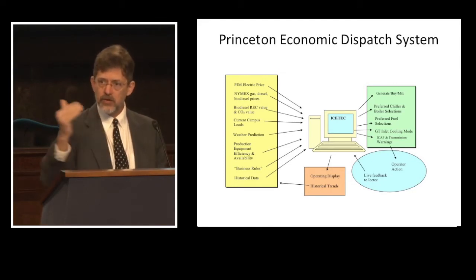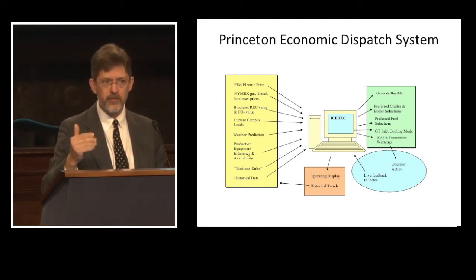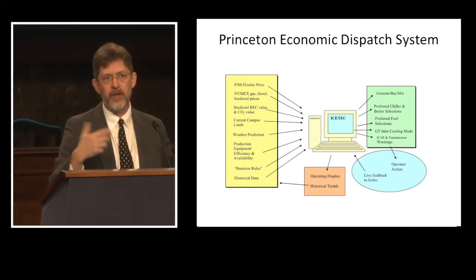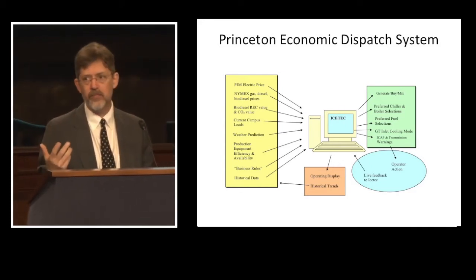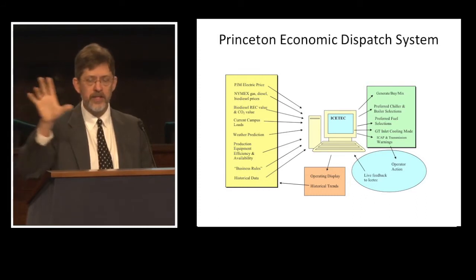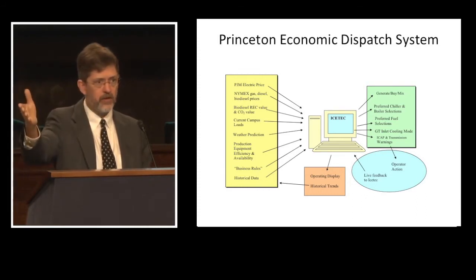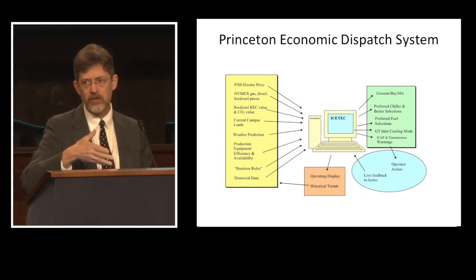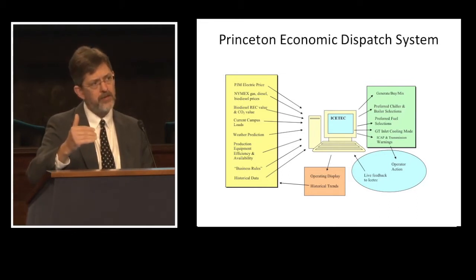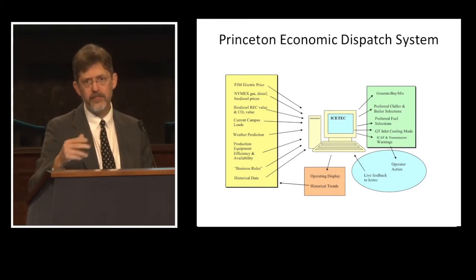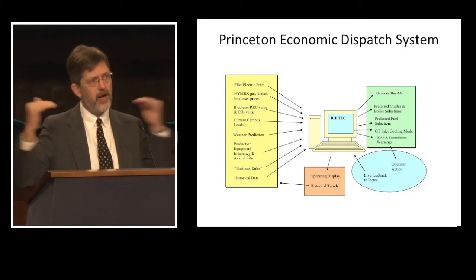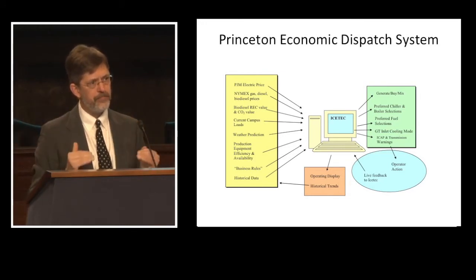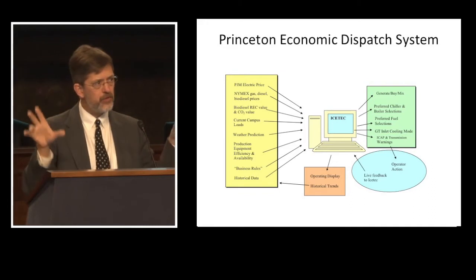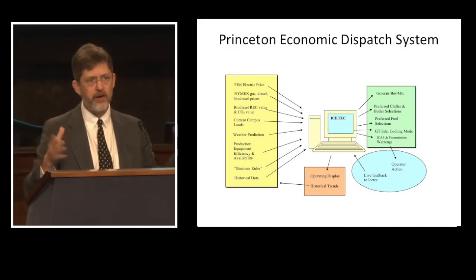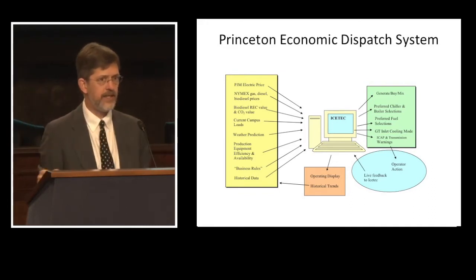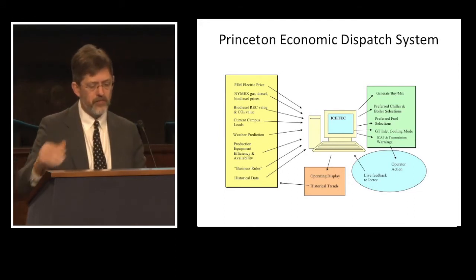So we're not just looking at the design numbers, we're measuring in real time. We're very thoughtful and careful with our equipment, but by operating them at different times - maybe at full load it works great, at part load it doesn't work so great, or over time it's degraded simply by normal operation - we very carefully measure how it performs at this load point. Even with two equal pieces of equipment, which performs better under the demands we're offering it today? That's where we're most thoughtful and careful.